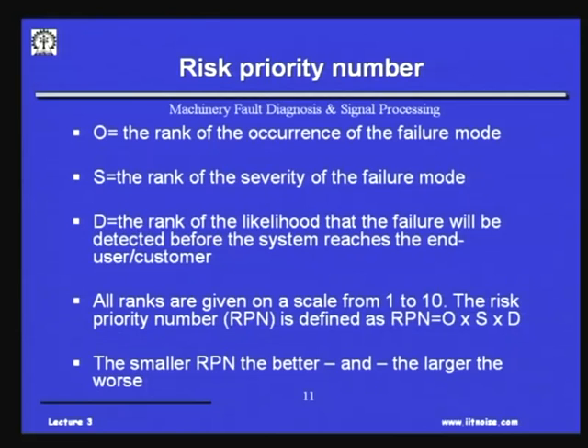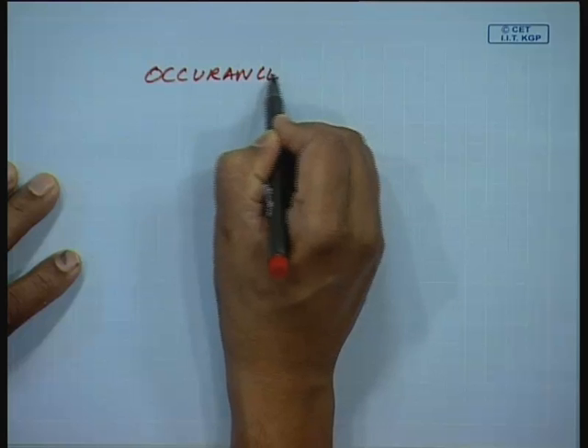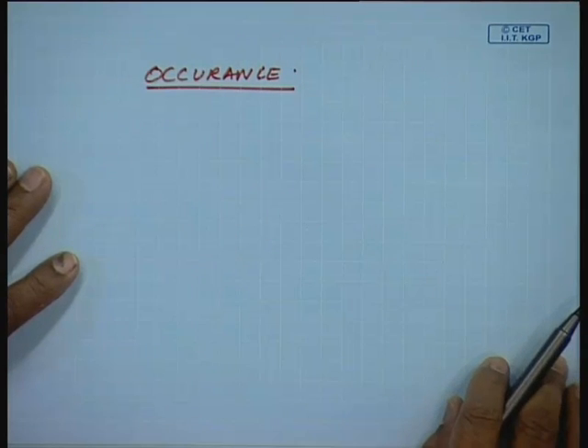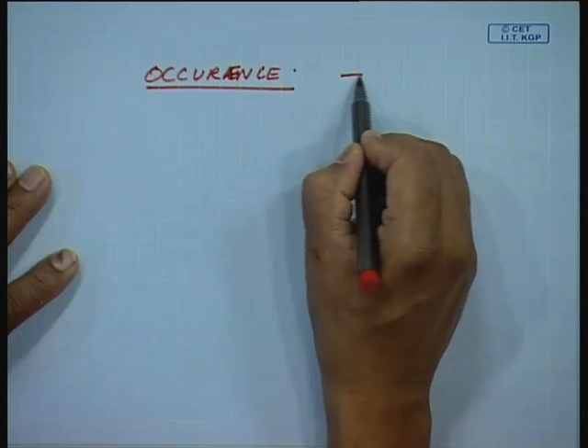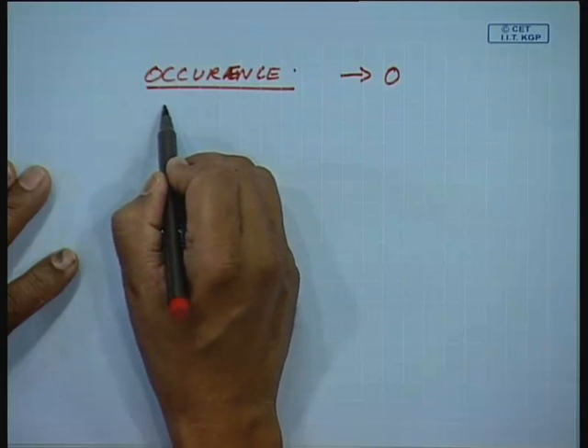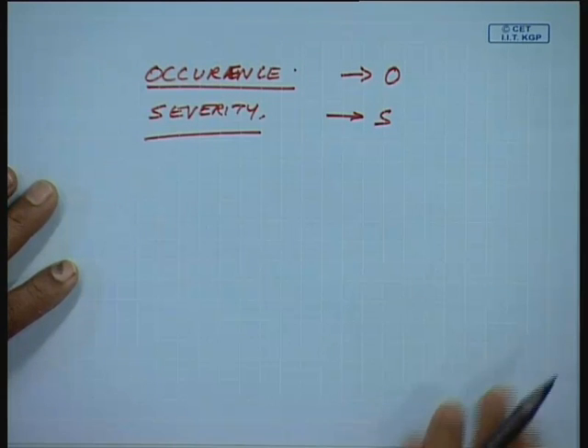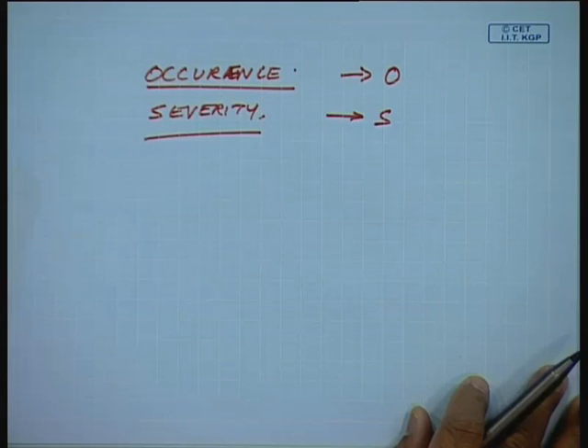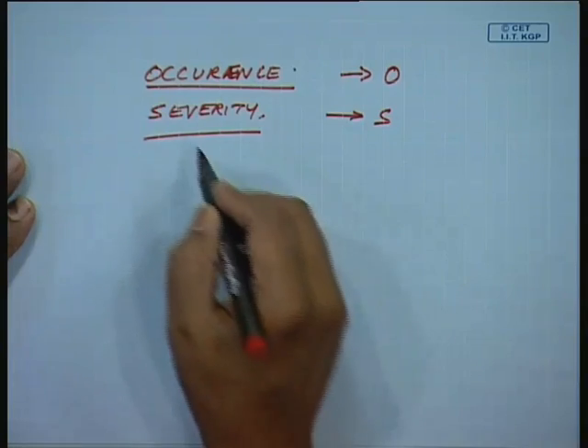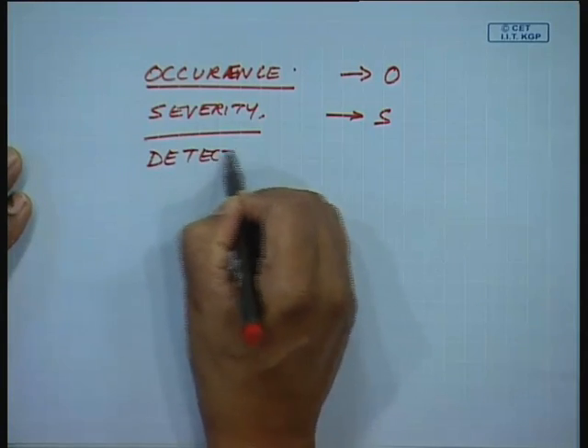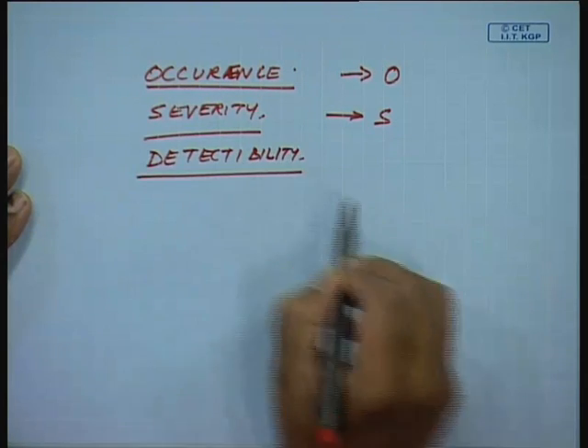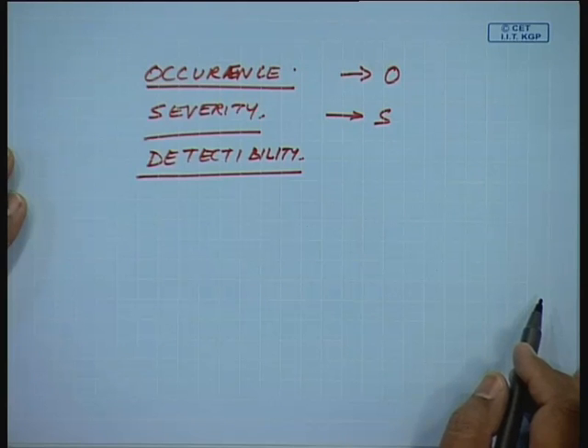The RPN number is the most important output from FMECA. This RPN number depends on three parameters. One is O — the rank of occurrence of the failure mode, meaning how frequently this system is going to fail. Another is S — the severity of the failure. If there is a failure in this component, how severe is it? Is it going to affect other components in the process?